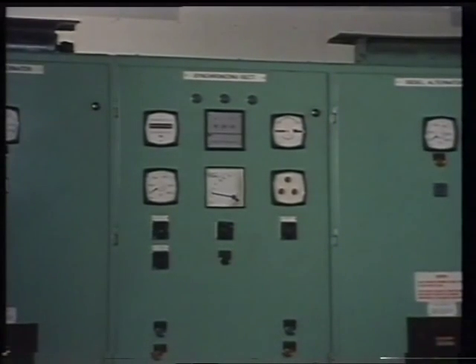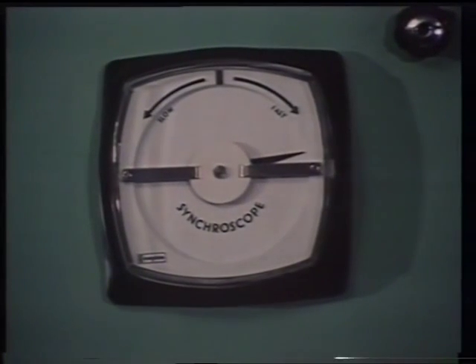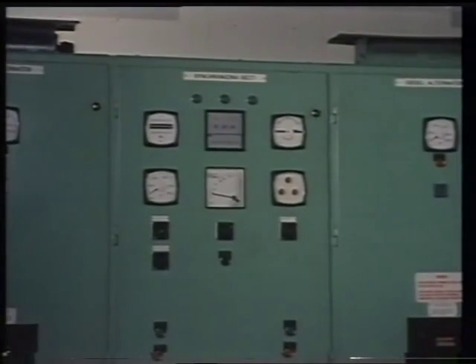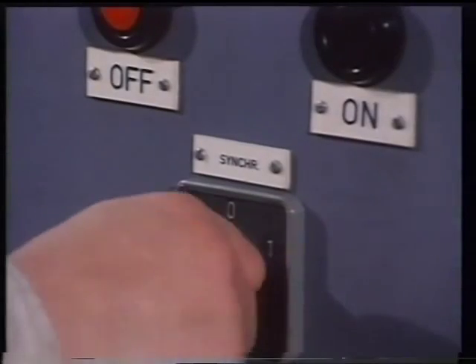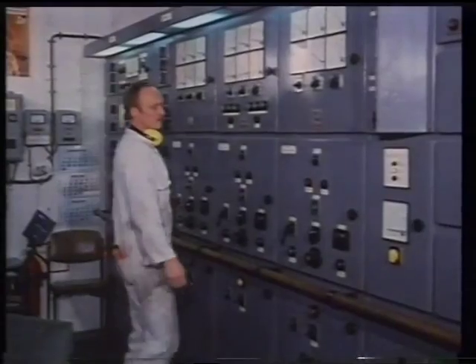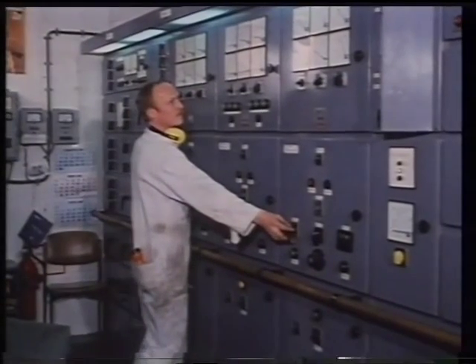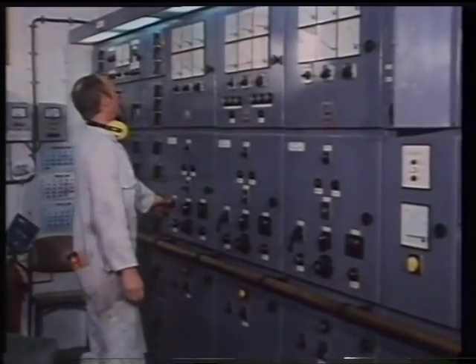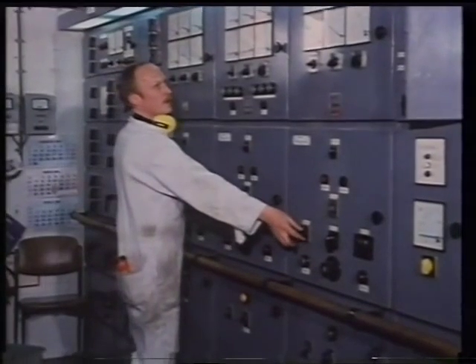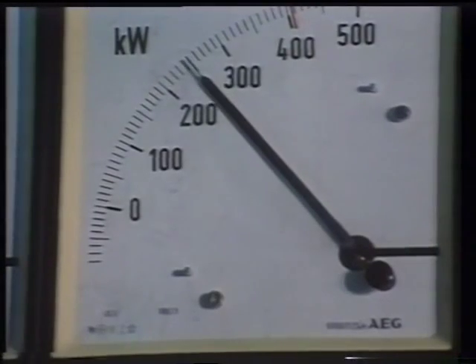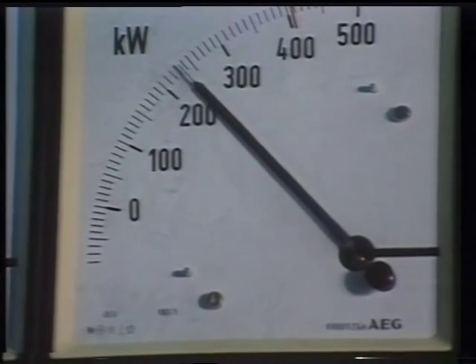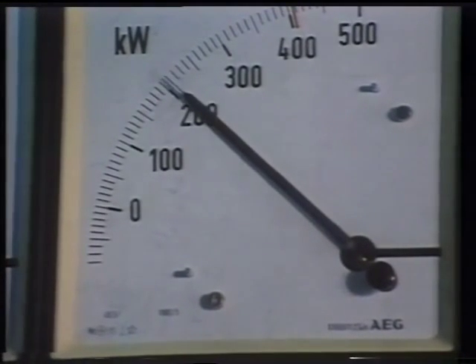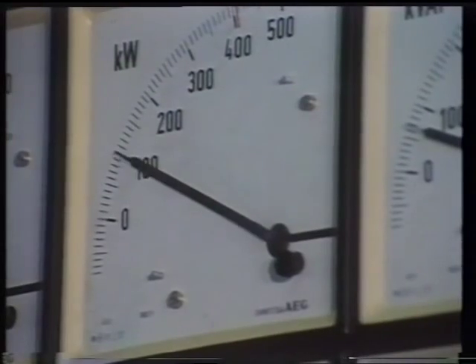Most synchroscopes use the 12 o'clock position of their circular display to show the point of synchronization. The synchronizing equipment can now be switched out and the load shared between the two alternators. The governors of the two prime movers can be adjusted so that the two alternators will take about equal share of the total load, as shown on the kilowatt meters.